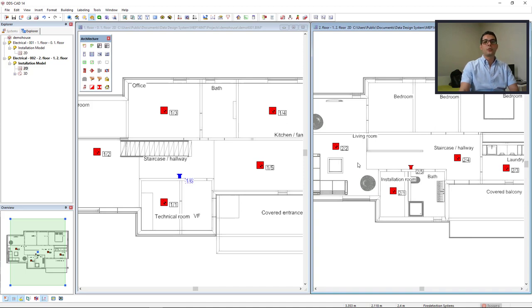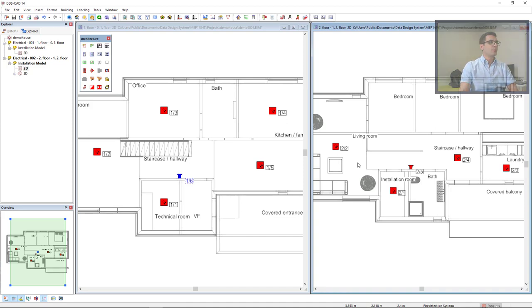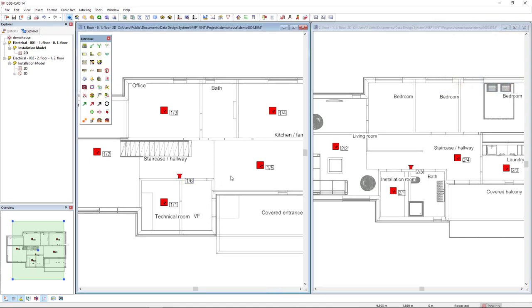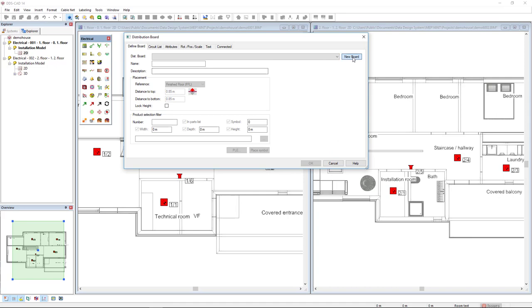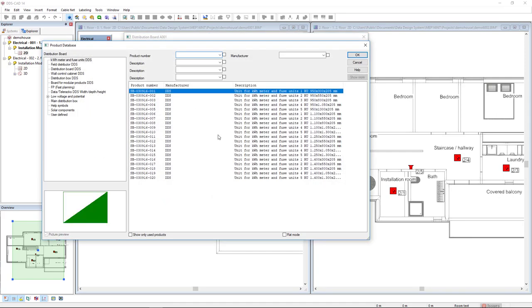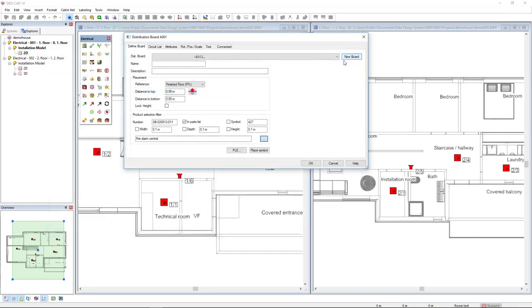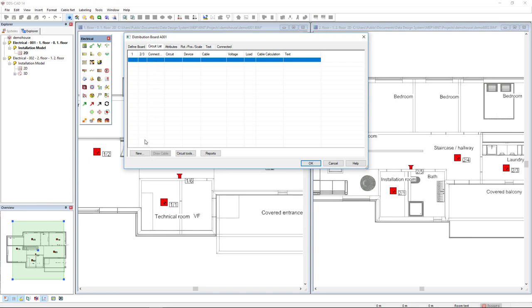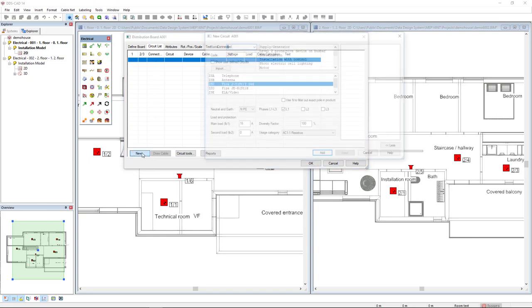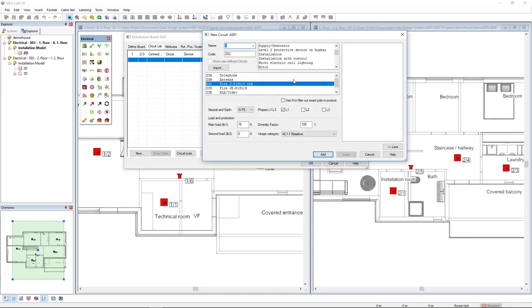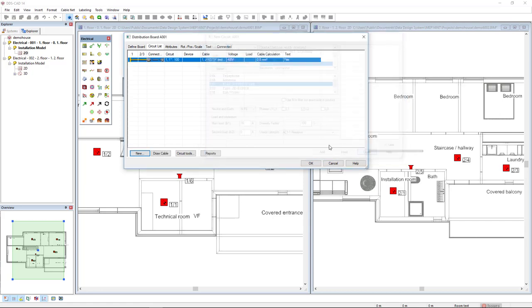Now that all my objects have the correct indication in the model, I would like to create a system. To do so, I will create a board. I create a new board and in the product database, I will select the category low voltage and potential and I'll select the subcategory fire alarm. I'll select this fire alarm central. I'll create a circuit, a new circuit from devices category. I will select the subcategory fire JB red. I click add and I can close.